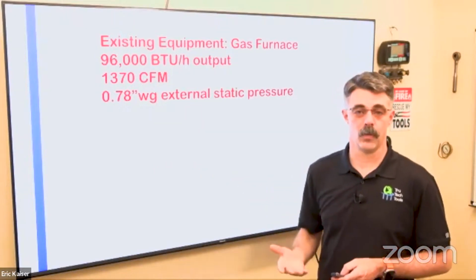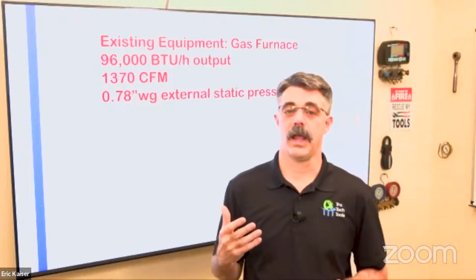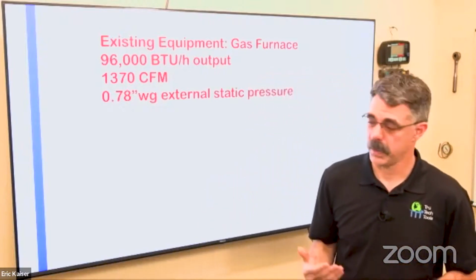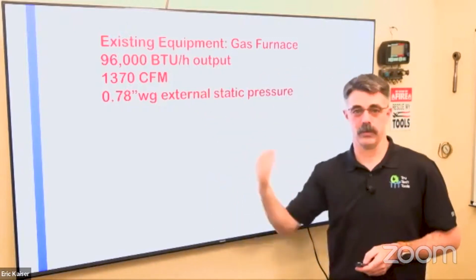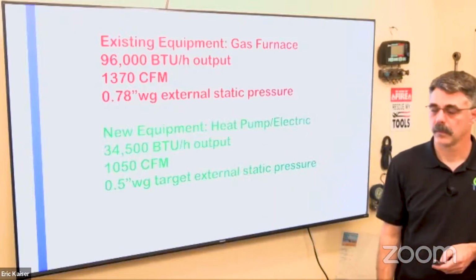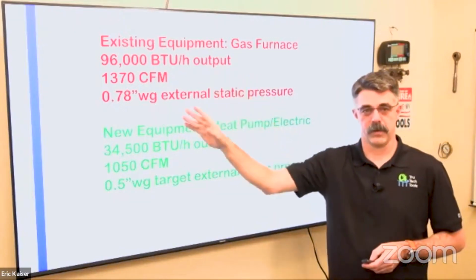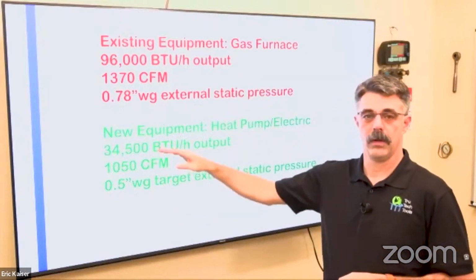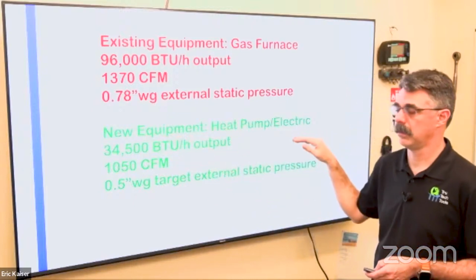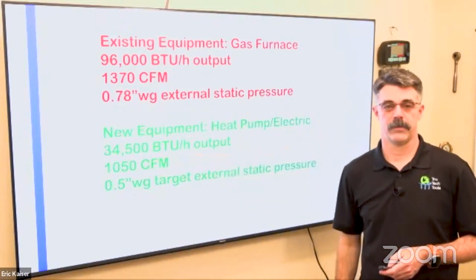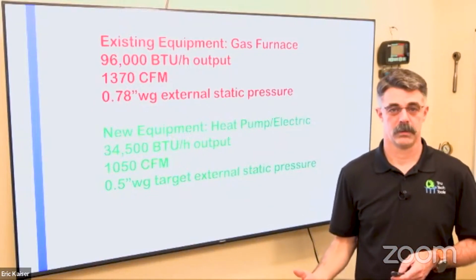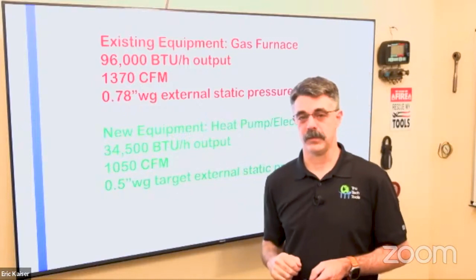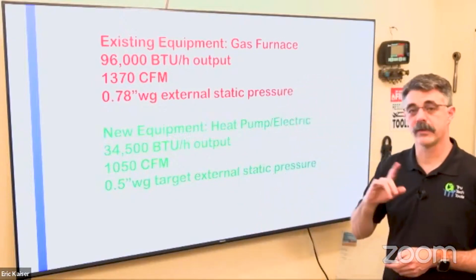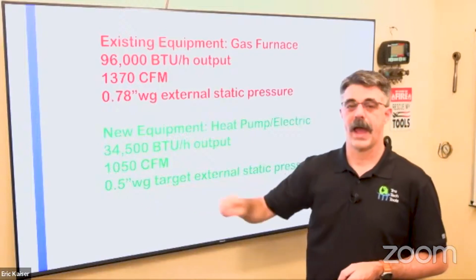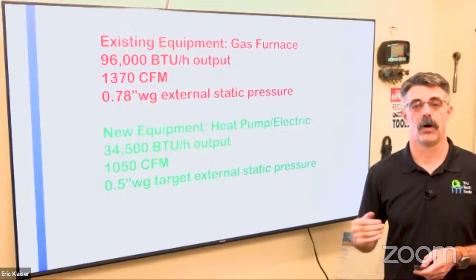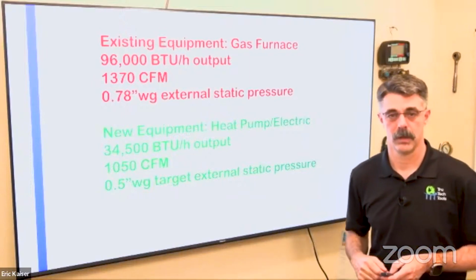Now, we did all the work. We figured out that we can put in a much lower capacity unit because the house doesn't need that. This just happened to be what somebody put in. Okay. And I can speak to this one because this is very, very close to what my house is. Now, new equipment going in, heat pump and all electric, right? We need 34,500 BTUs per hour of output, all right? To get that, we're going to run 1,050 CFM through that equipment. And we have a target in mind. We have a target we want to meet of half an inch of water column external static pressure on that new unit going in.